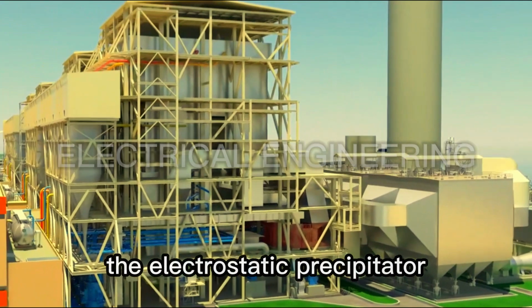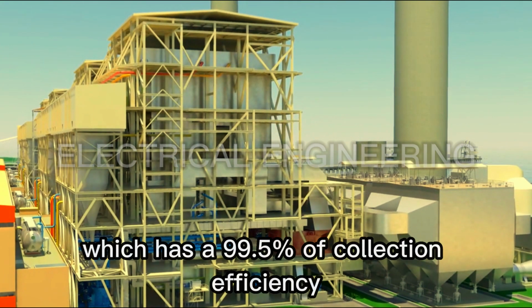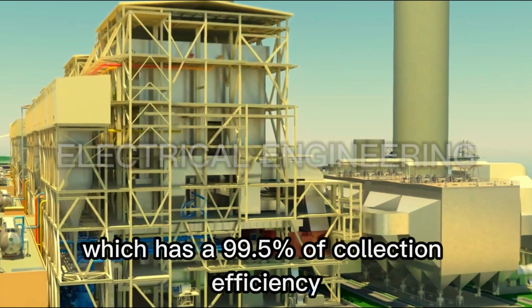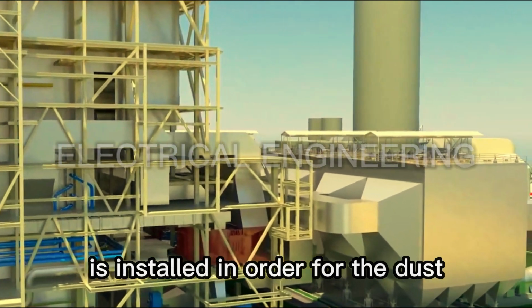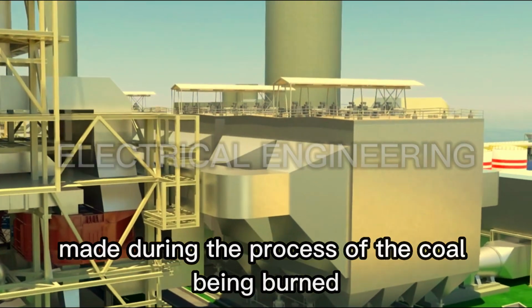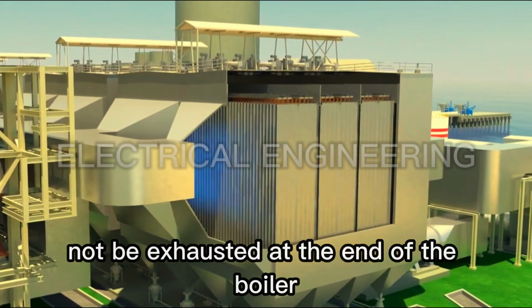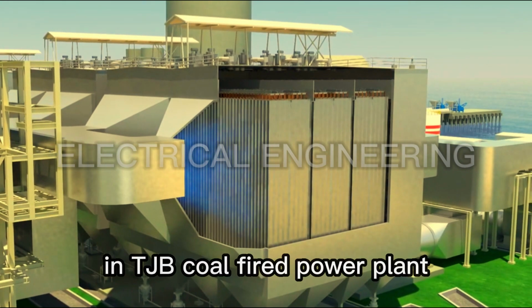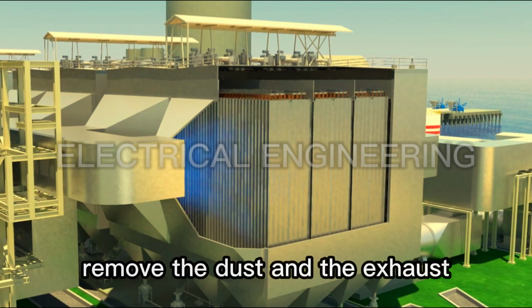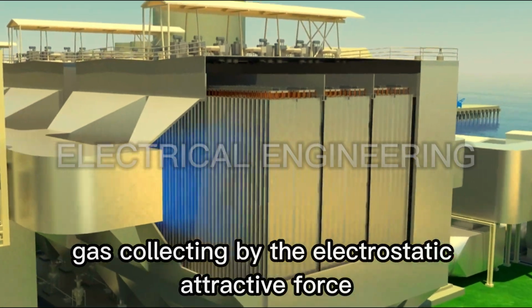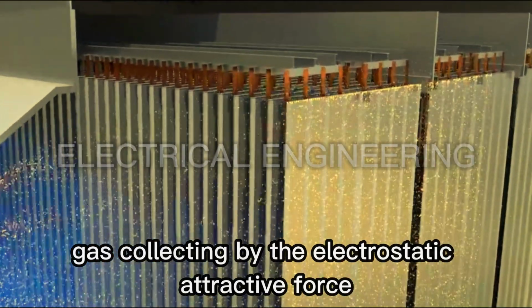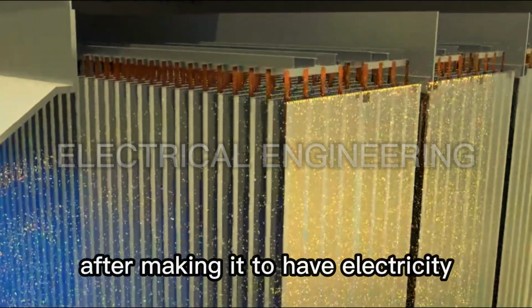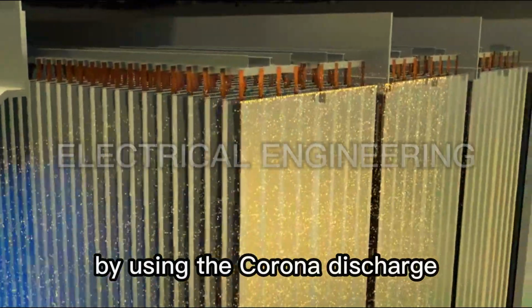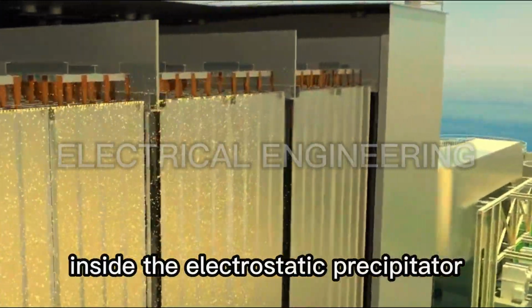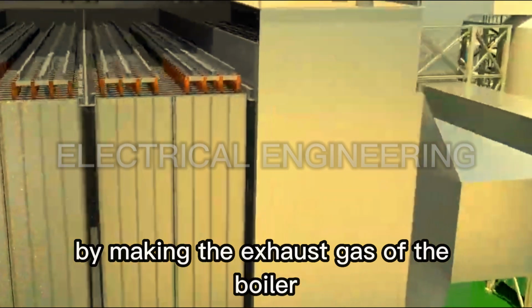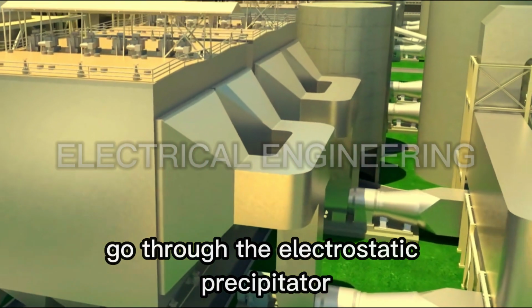The electrostatic precipitator, which has 99.5% collection efficiency, is installed so that the dust produced while the coal is burned is not exhausted at the end of the boiler in TJB coal-fired power plant. It removes the dust from the exhaust gas by collecting it with electrostatic attractive force, after giving it an electric charge using the corona discharge inside the electrostatic precipitator, as the exhaust gas of the boiler goes through it.